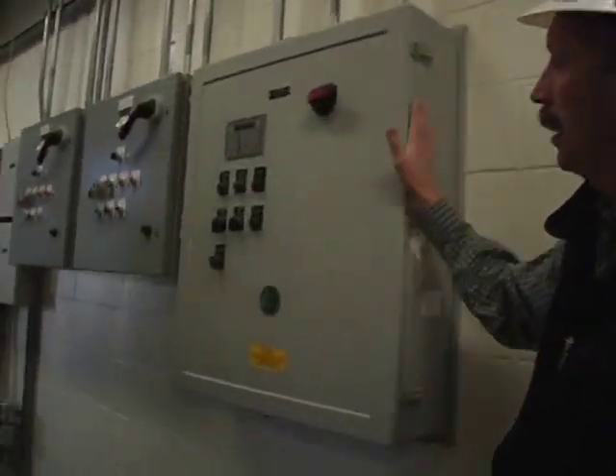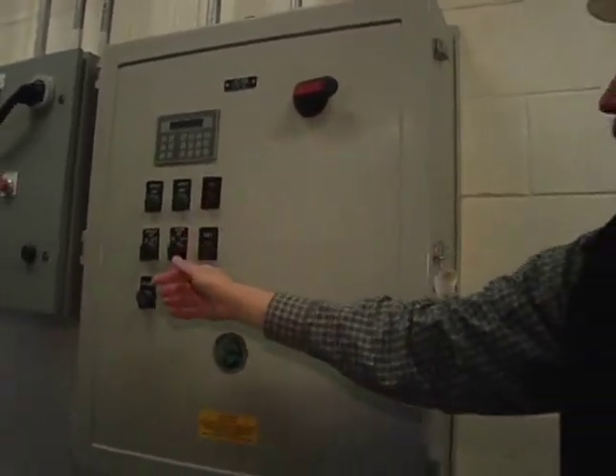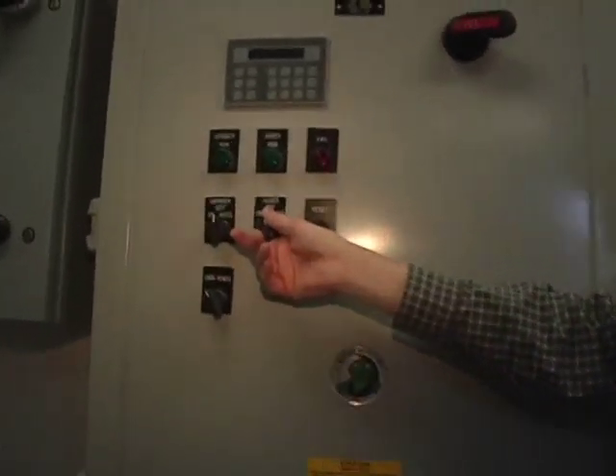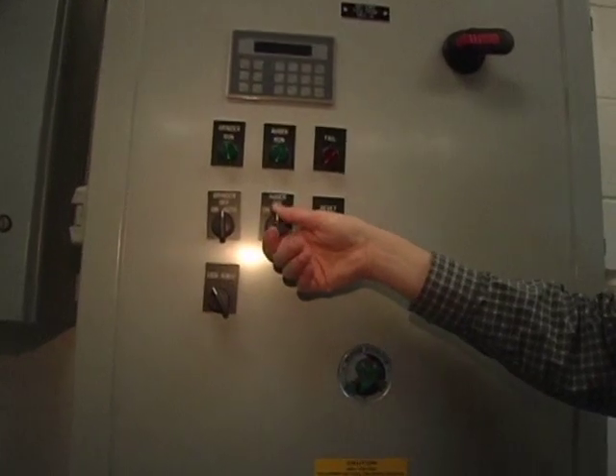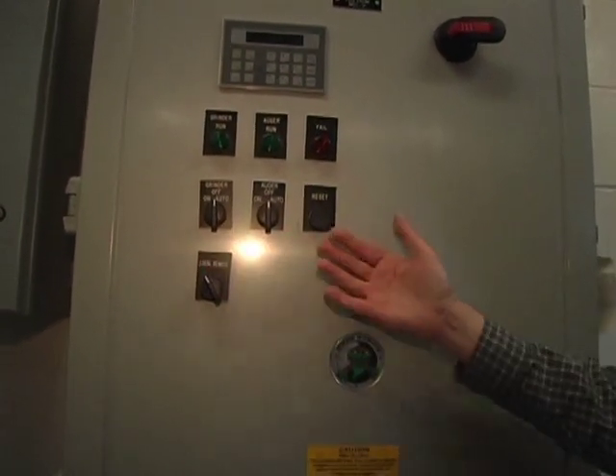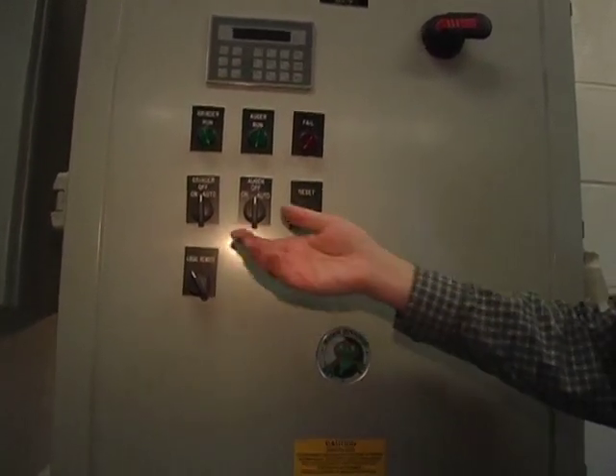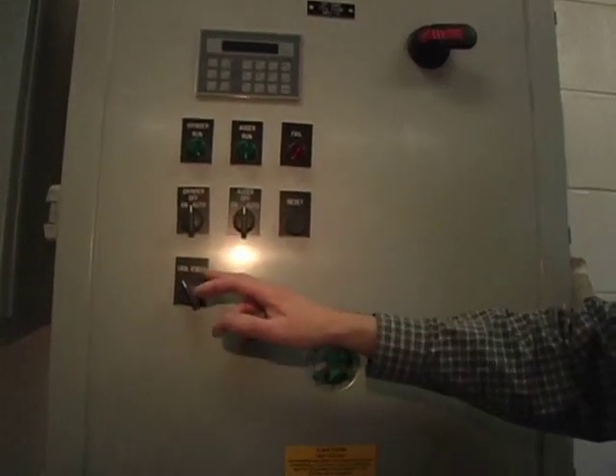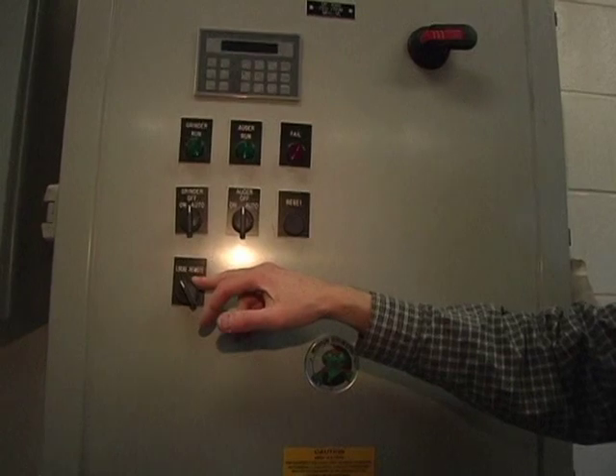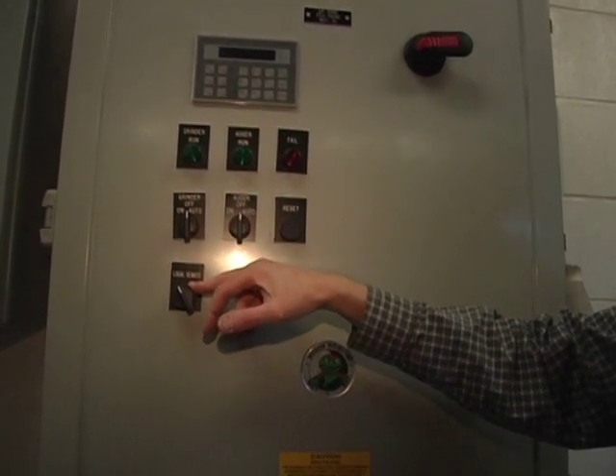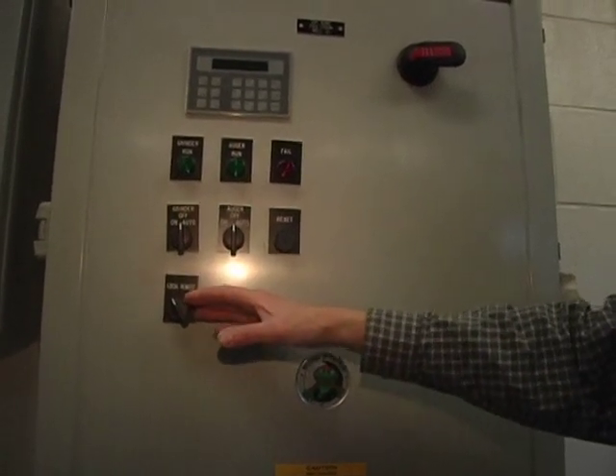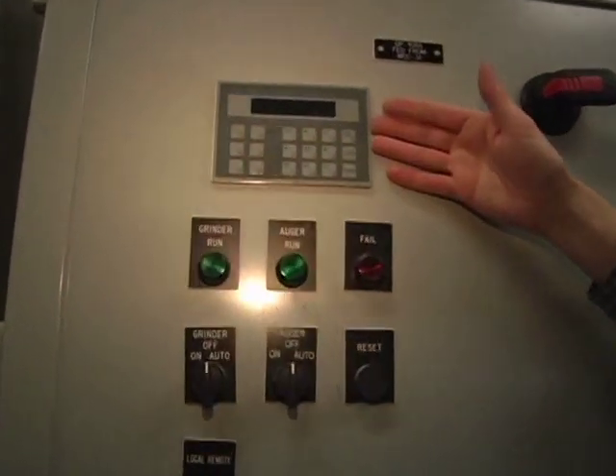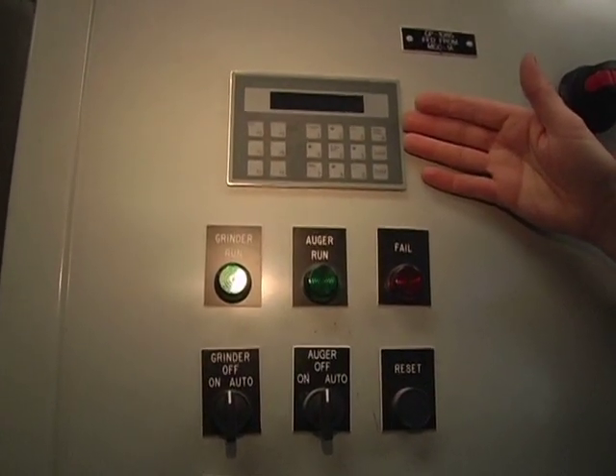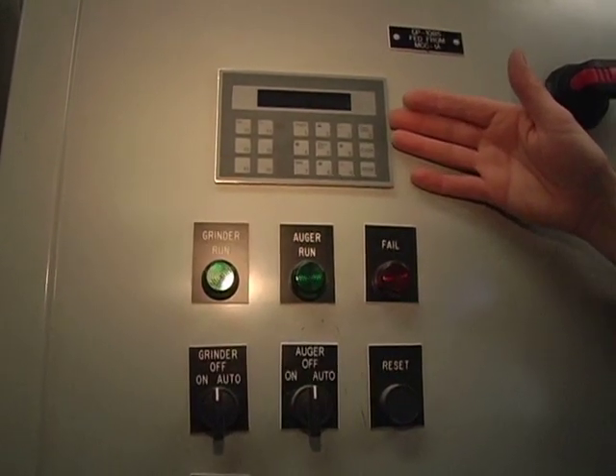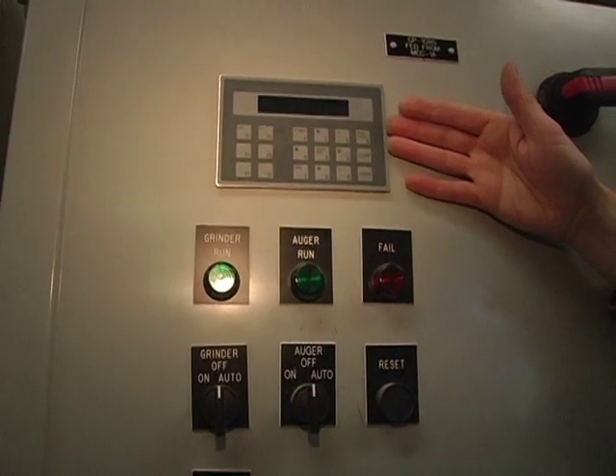Beyond this panel is the screenings wash press control panel. Here again, you've got a disconnect for the system, on-off-auto indications determining the mode of operation for the equipment, and local-remote, meaning that if it's in the local position, the control is here at this panel. You can control it through the on-off-auto selector switches, and if this is placed in the remote position, then that transfers control of the equipment to SCADA so it can be started and stopped automatically from any one of the operator control panels. You've got a keypad on the top part of the panel, which is used to input information into the system, things like the timing sequence for the forward and reverse cycling of the auger, as well as the grinder itself.